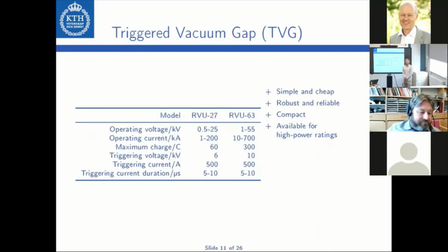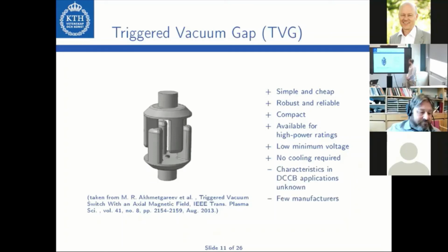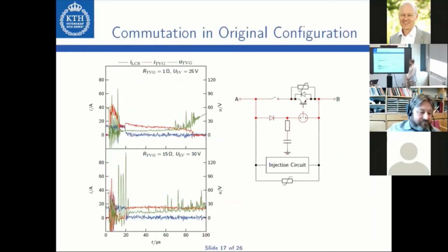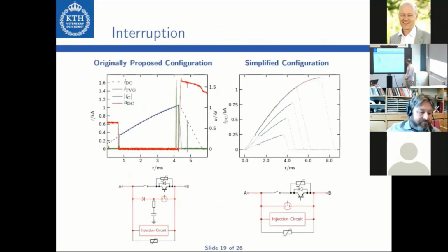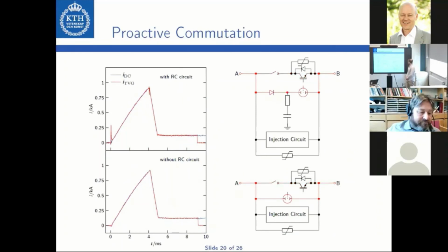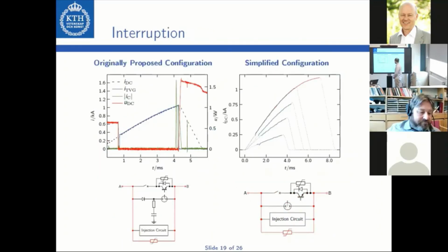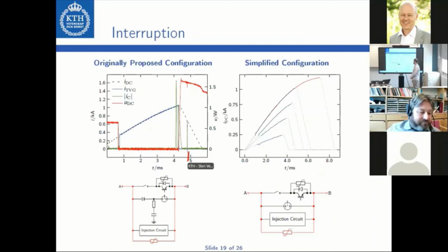My first question is about the spikes in the measurements. You said, in some slide where you performed an interruption, there was a loss in voltage during the suppression time—let's see, maybe it was the pre. Okay, there were spikes there, for instance here, yes. So at around 4.7 milliseconds in the left-hand plot, we see a downward spike in the voltage across the breaker and an increase in the current in the injection circuit. Yes. So that seems—do you have a reason?